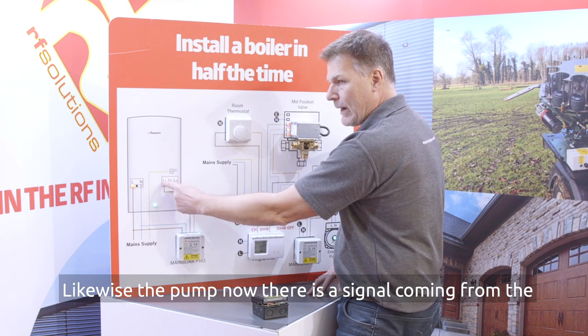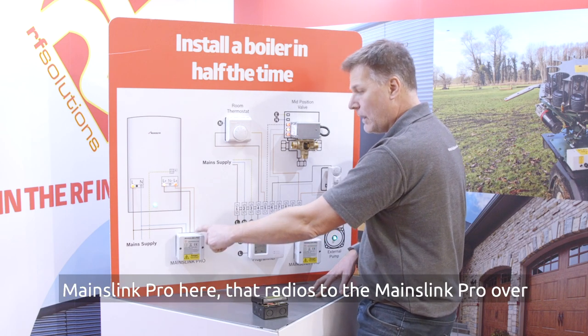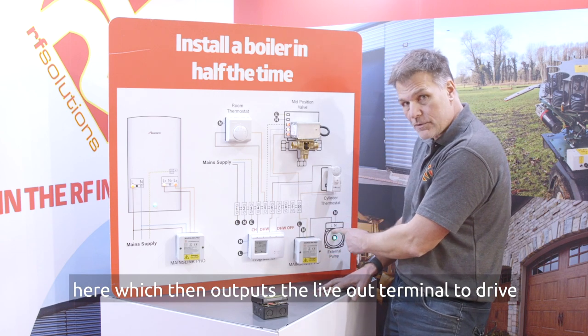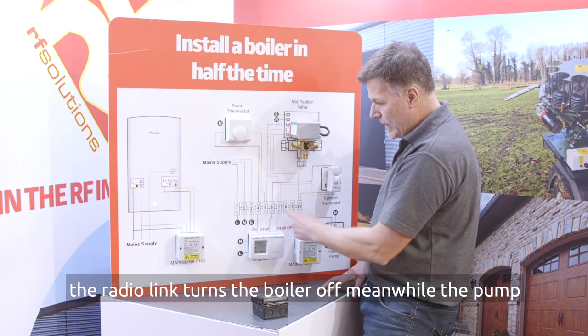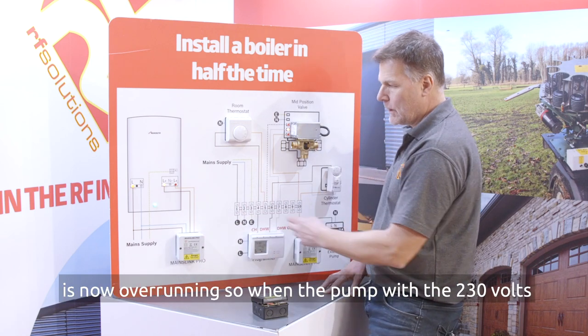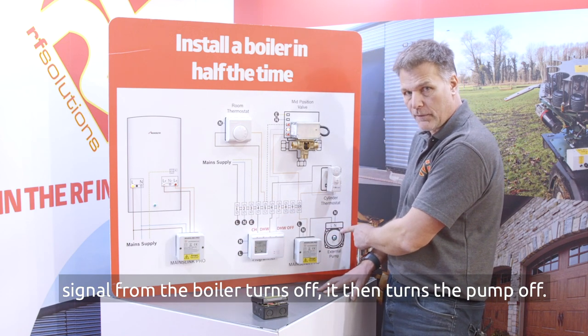Likewise the pump overrun signal coming from the boiler — 230 volts goes into the live in terminal at the Mainslink Pro here. That radios to the Mainslink Pro over here which then outputs the live out terminal to drive the pump on. When I turn the thermostat down, the radio link turns the boiler off. Meanwhile the pump is now overrunning, so when the pump 230 volt signal from the boiler turns off, it then in turn turns the pump off.